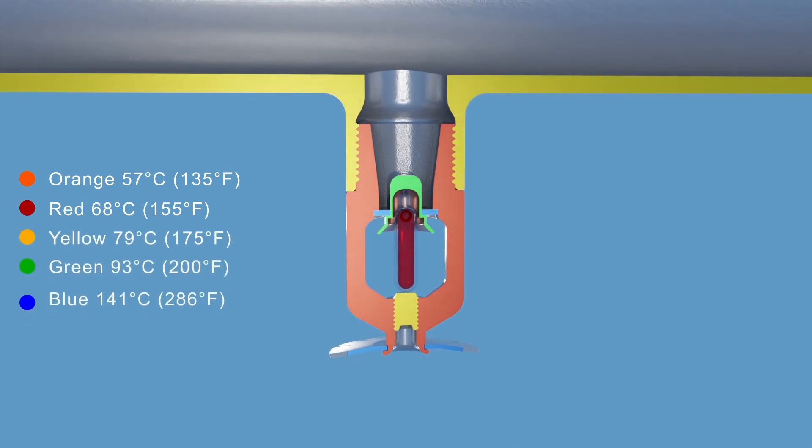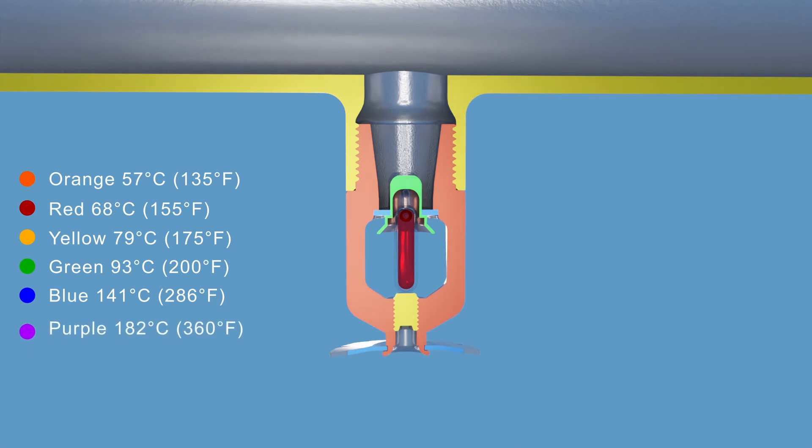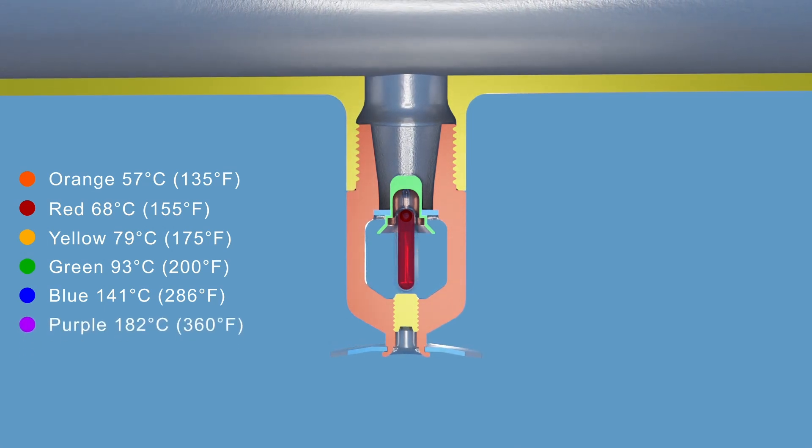These color codes help in quickly identifying the temperature rating of the sprinkler head. The most common glass bulb color is red that breaks at 68 Celsius or 155 Fahrenheit.